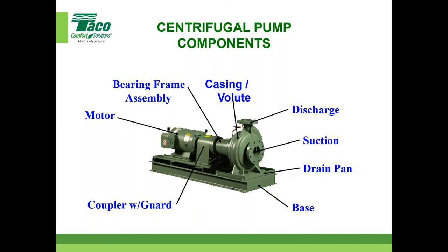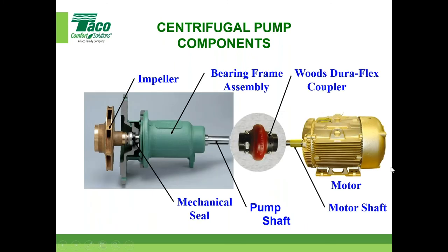And we're going to talk about the bearing frame in greater detail right now, by the way. So here's kind of a breakdown of what we were talking about. And that great question about the impeller thickness, you can kind of see it right there. It's hard to tell, and this isn't that big of a pump, so it probably even changes on different size pumps. I will say this: if the system's designed correctly and there are no NPSH issues and it's a pretty clean water system, usually the impeller is going to last as long as, if not longer than, anything else on the pump. We don't really get many returns of impellers. There are always circumstances out there, and usually NPSH is one of them. But these impellers are pretty sturdy pieces of equipment, and again, mostly bronze material. Excuse me. One of the items that obviously is on wet end pumps is the mechanical seal.